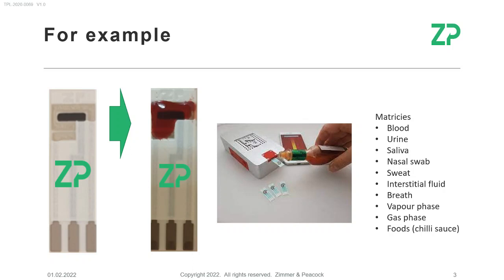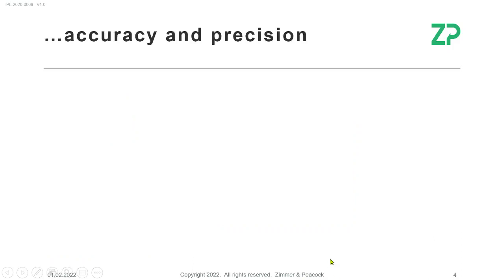Because it's not the same as a temperature sensor, where you can characterize temperature sensors, and how they perform is somewhat independent of the sample itself. So if you were measuring temperature in cheese or temperature in water or temperature in the air, the temperature sensor is going to behave the same way, but it's not the same for a biosensor.